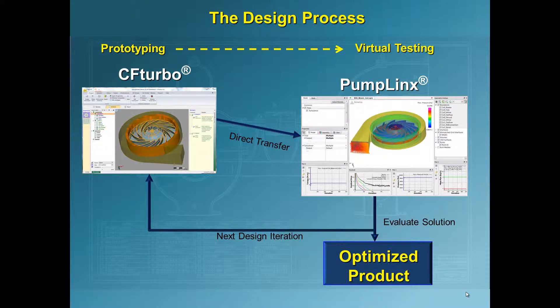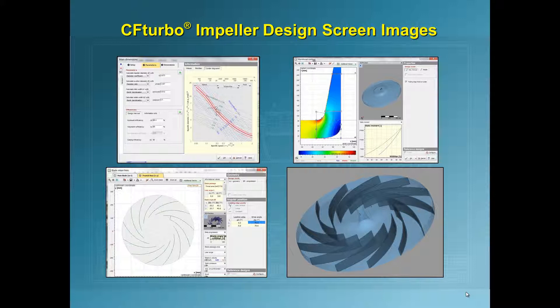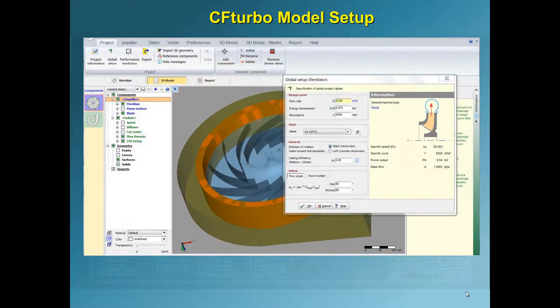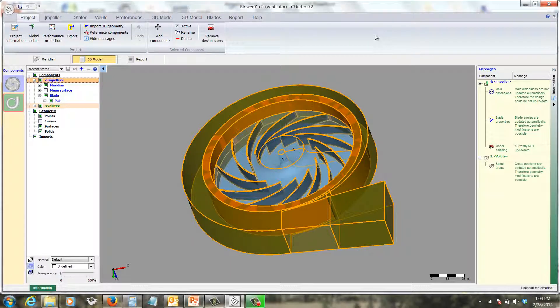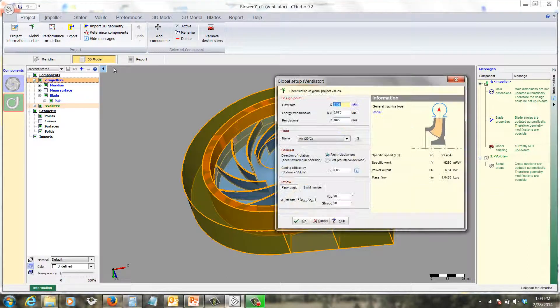This continues until the blower is optimized. Here are some screenshots of some of the panels in CF Turbo. The design process begins by specifying the basic performance requirements, such as flow rate, head, RPM, fluid type, and efficiencies. So here we are in CF Turbo, and this is the blower model, which is almost finished. This is the global setup panel, where we input the flow rate, head, and other flow parameters. Based on empirical correlations from experimental data, CF Turbo calculates the main device dimensions, and the user proceeds through the design procedure to arrive at the final design.